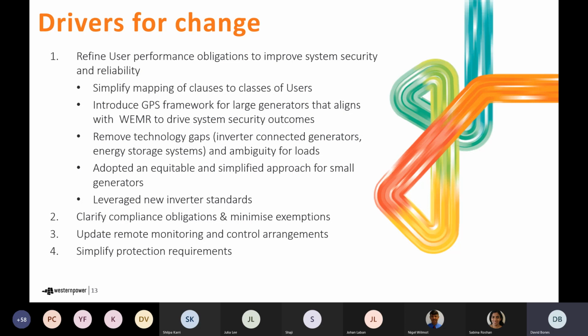As we spoke of, the process has now gone through the WEM review process and ended up with revisions to the generator performance standard framework. So now you have within the WEM rules the requirement for large generating systems that are transmission connected and participating in the market to develop performance standards through the WEM rules process. Putting that framework in place was really driven by a need to make sure that those large generators have appropriate technical requirements, again, to provide appropriate system security outcomes.